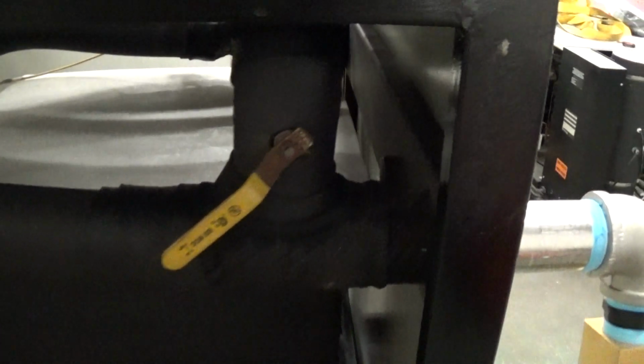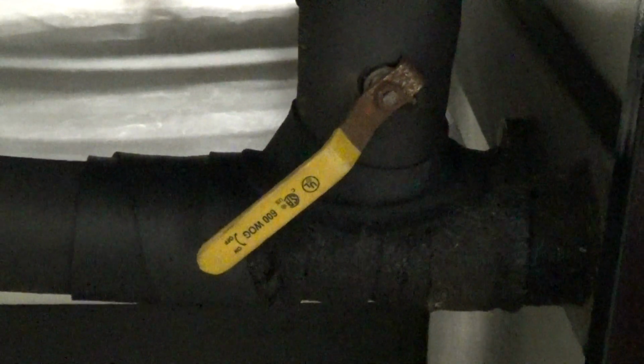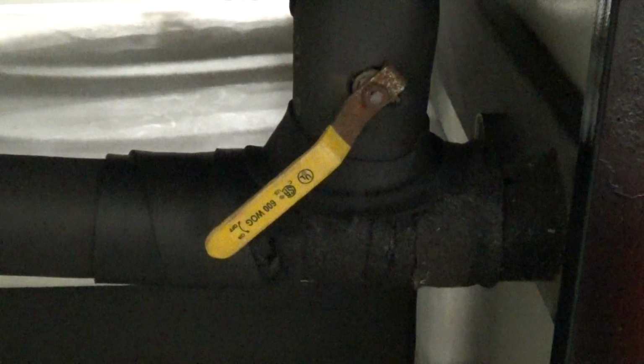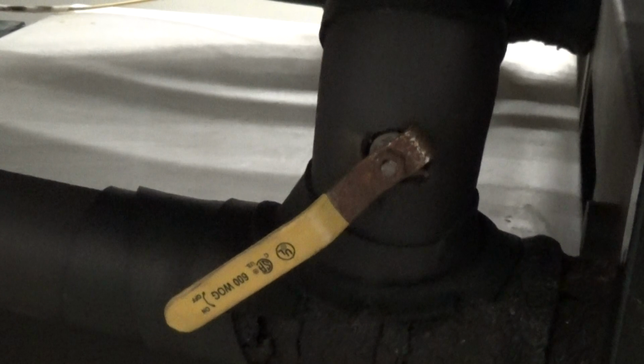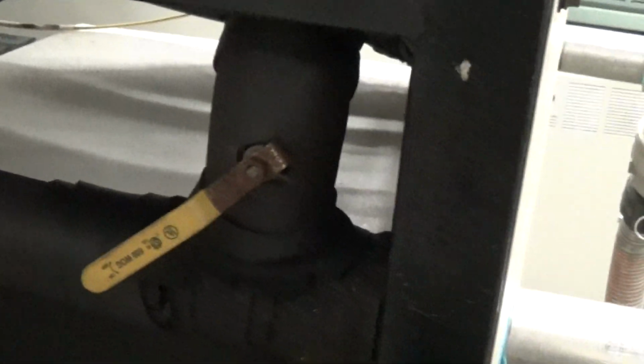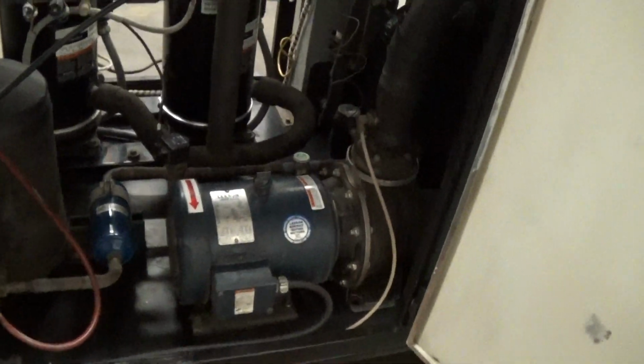This chiller already has an internal flow bypass. We're going to ship it at the 50% cracked open number. That ultimately can be adjusted depending on several process parameters. If your process machine has solenoid valves on it that open and close, it's important to have this open, not completely shut, so you have sufficient flow coming back to the chiller at all times. The glycol pump runs all the time. You have our 1 TXV thermal expansion valve for a typical operation, typical plant user. You don't really need to worry about that. That's more for an HVAC tech if you ever have a problem down the road.